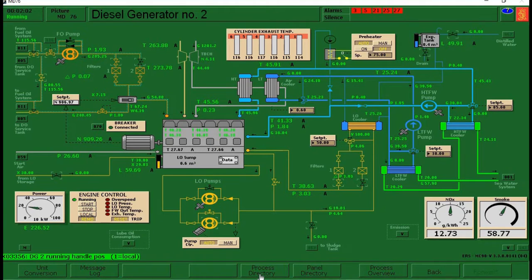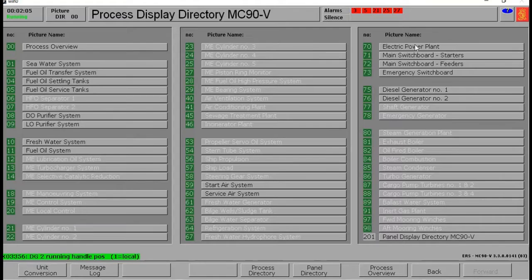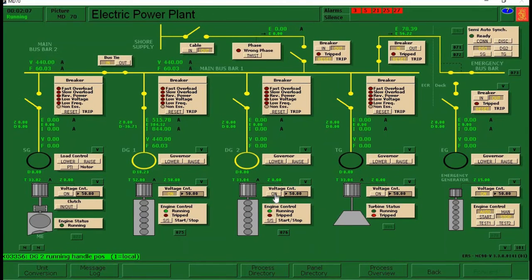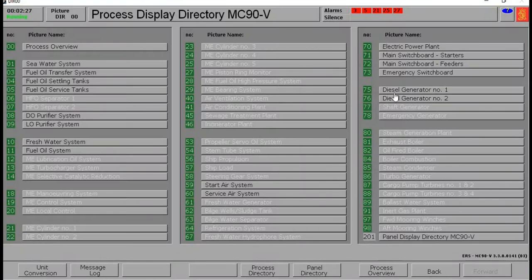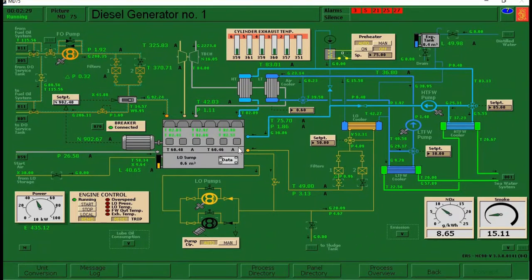Then we need to synchronize it. So let's go to electric power plant. Connect the voltage control here on, and DG2 in semi-auto sync. Then connect. So our running diesel generator 2 here should connect to the main bus bar. Okay, this one. Okay, so let's go to diesel generator 1.